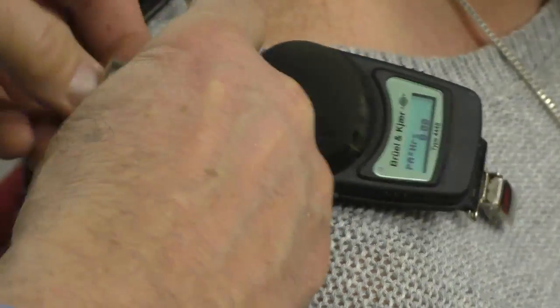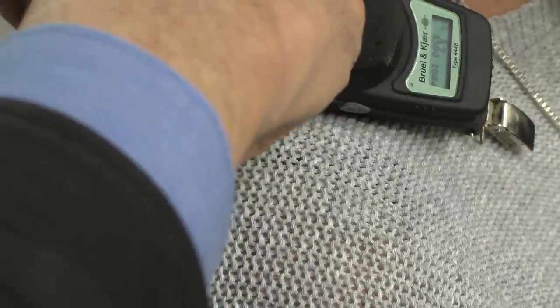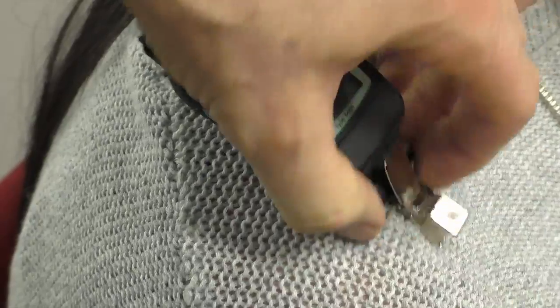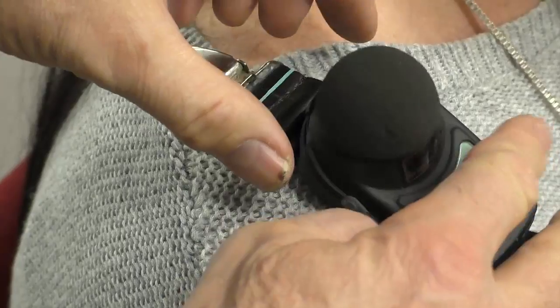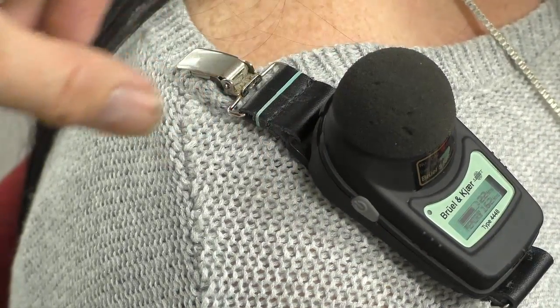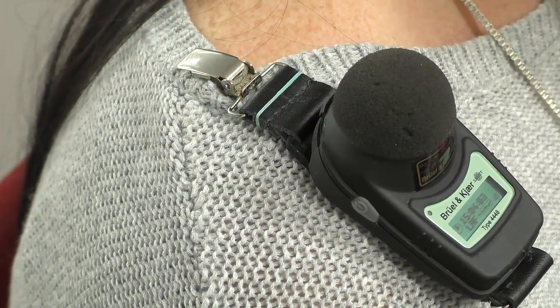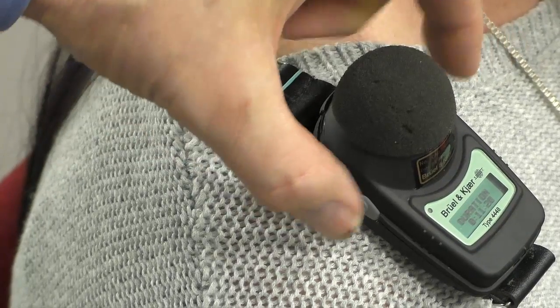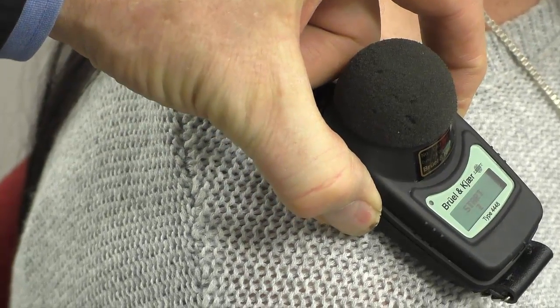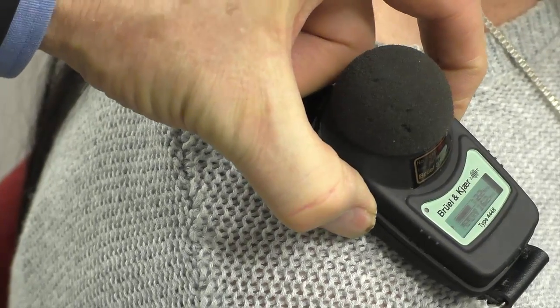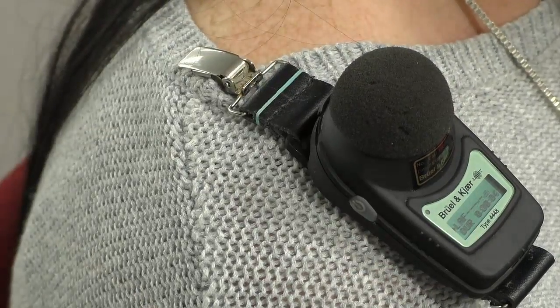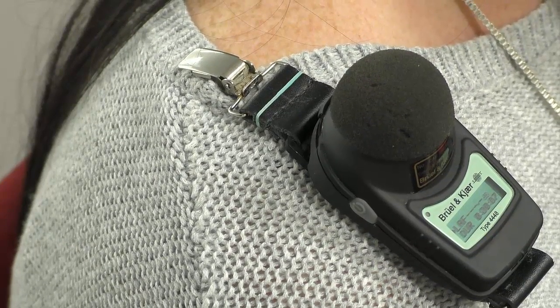Having calibrated the instrument, we now need to attach it. We just attach it to the clothing near the ear. I clip it on here, for example, and fold the fabric a little and clip it on down there. Now, you may need to use some safety pins, depending upon how much physical activity the person's involved in. Now we've attached it, we simply turn the instrument on, I hold both buttons, and it's recording. We've got the little play light. We can lock the instrument, of course, too.